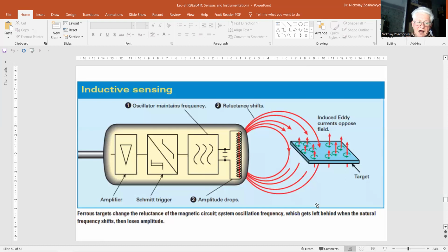Pressure and force are likewise determined by an elastic intermediate. The deformation or displacement of that element can be measured by an inductive sensor and is accomplished in various ways. For instance, the bending of a conductive membrane affects the reluctance of a magnetic circuit composed of this membrane and one or more coils. If the membrane is not conductive or ferromagnetic, small ferrite objects can be attached to both sides of the membrane, together with two coils forming a differential variable reluctance circuit.